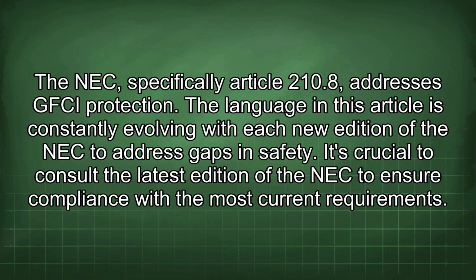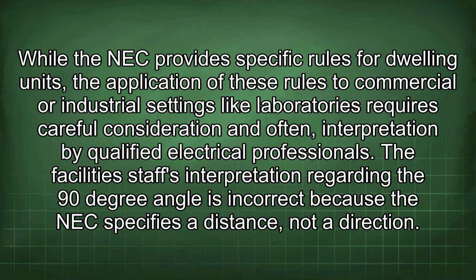The NEC, specifically Article 210.8, addresses GFCI protection. The language in this article is constantly evolving with each new edition of the NEC to address gaps in safety. It's crucial to consult the latest edition of the NEC to ensure compliance with the most current requirements. While the NEC provides specific rules for dwelling units, the application of these rules to commercial or industrial settings like laboratories requires careful consideration and often interpretation by qualified electrical professionals.